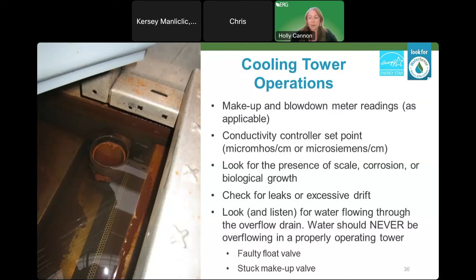You also want to look for scale, corrosion, biological growth, anything that may be indicating to you that the tower is not operating well. Look around the basin for any leaks or excessive drift. And lastly, you'll want to look and listen within the overflow drain to see if there's any water flowing. Towers have a blowdown line that water should be flowing to. They also have an overflow drain, and that one should not have water flowing to it ever. It's strictly there to prevent flooding in case of a malfunction. So if you do see water flowing to that overflow drain, like in this picture, that's a sign you've got a stuck makeup valve or a float valve or something going wrong. So you definitely want to look into that.